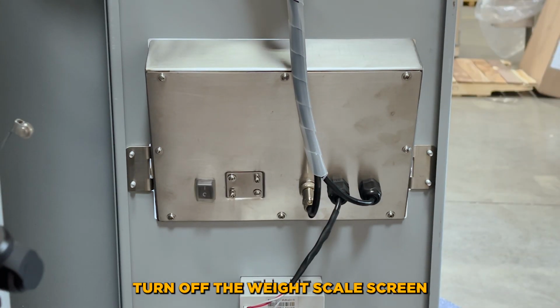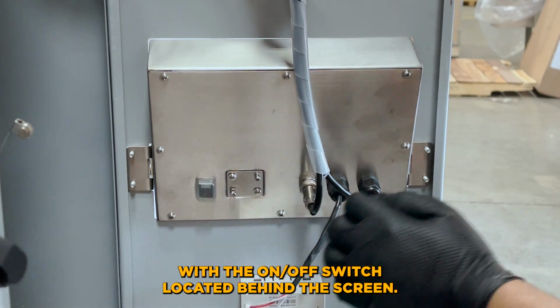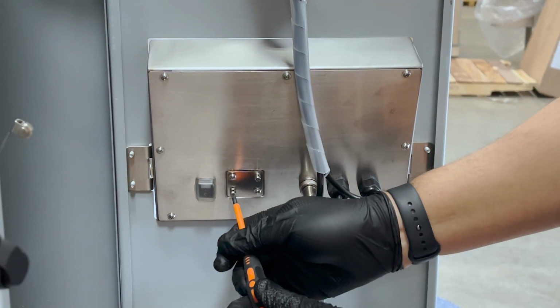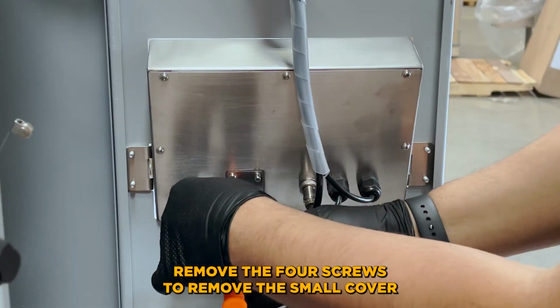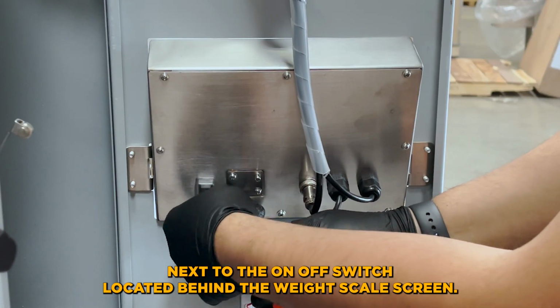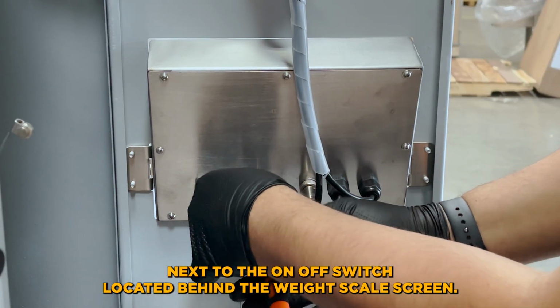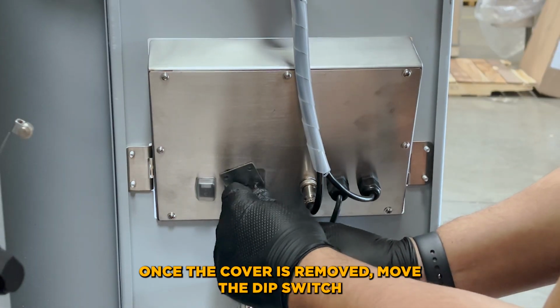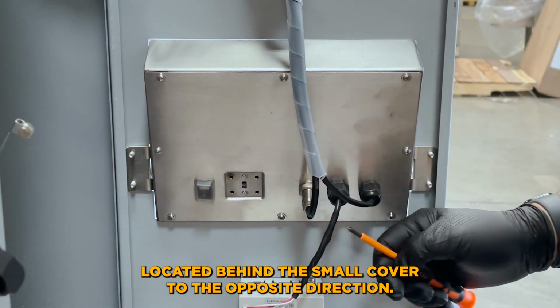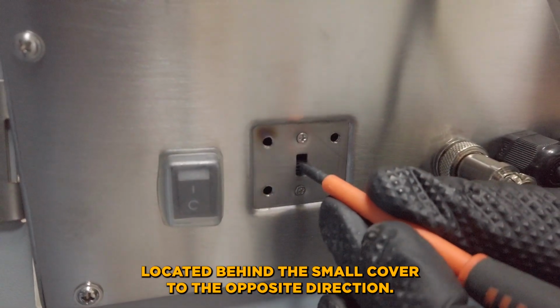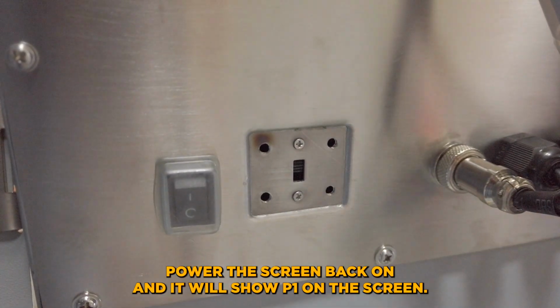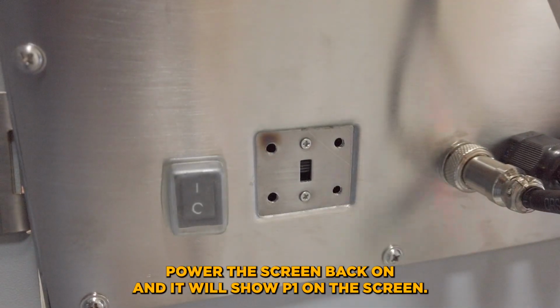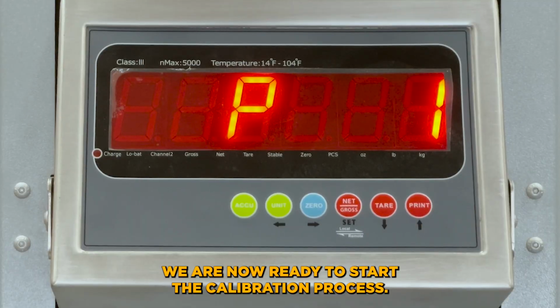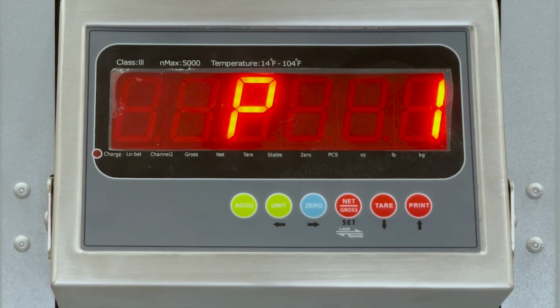Turn off the weight scale screen with the on-off switch located behind the screen. Remove the 4 screws to remove the small cover next to the on-off switch located behind the weight scale screen. Once the cover is removed, move the dip switch located behind the small cover to the opposite direction. Power the screen back on and it will show P1 on the screen. We are now ready to start the calibration process.